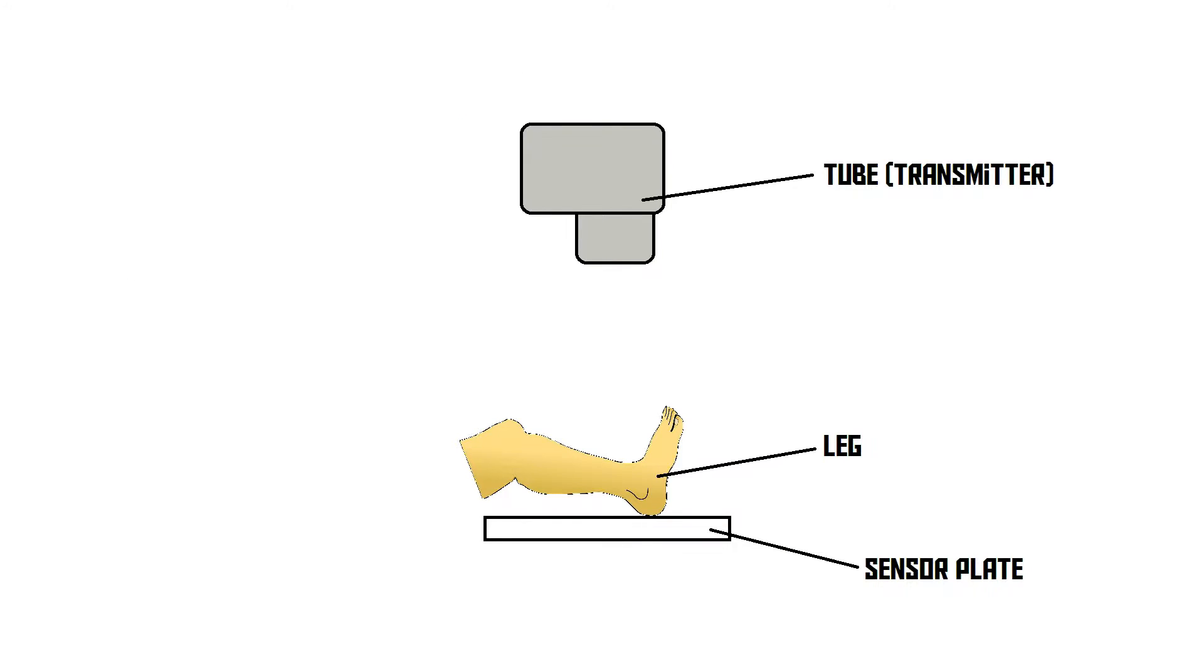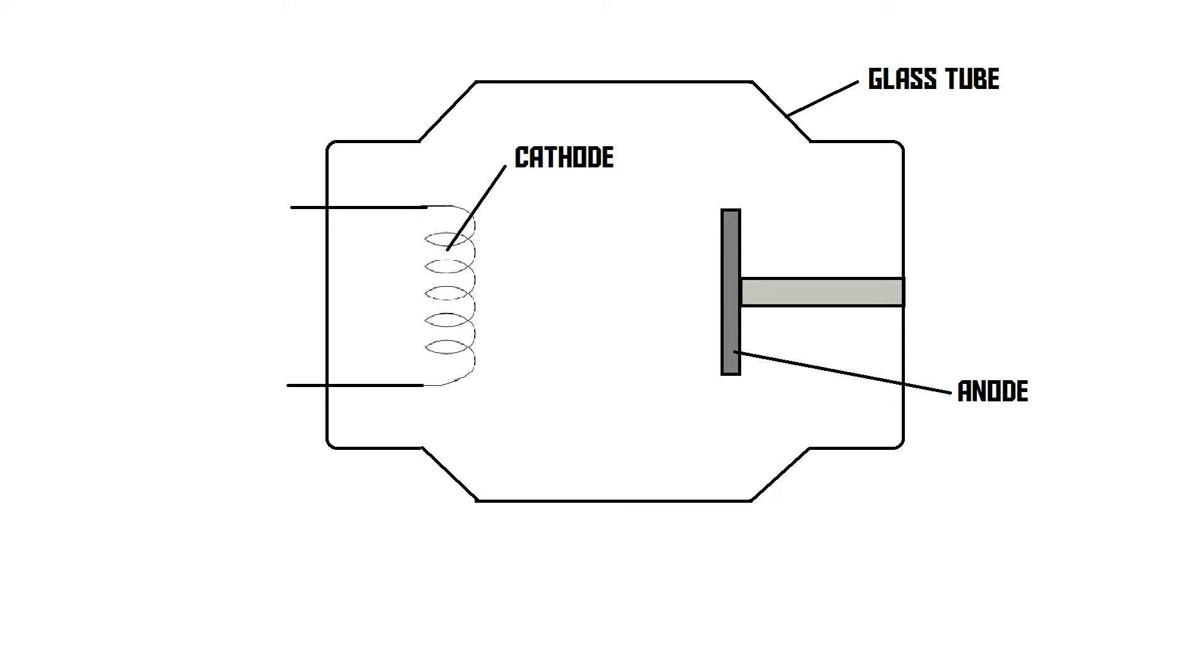An X-ray setup relies on two components, a tube and a sensor. The tube is a device that produces the X-rays and sends them through the body of the patient. This tube is made out of glass. Inside it, there's a vacuum. This is required for producing X-rays.